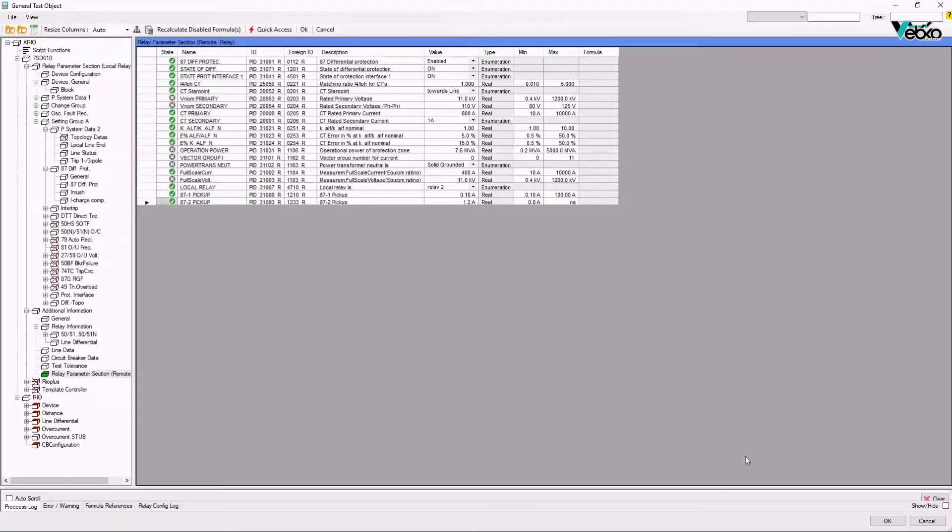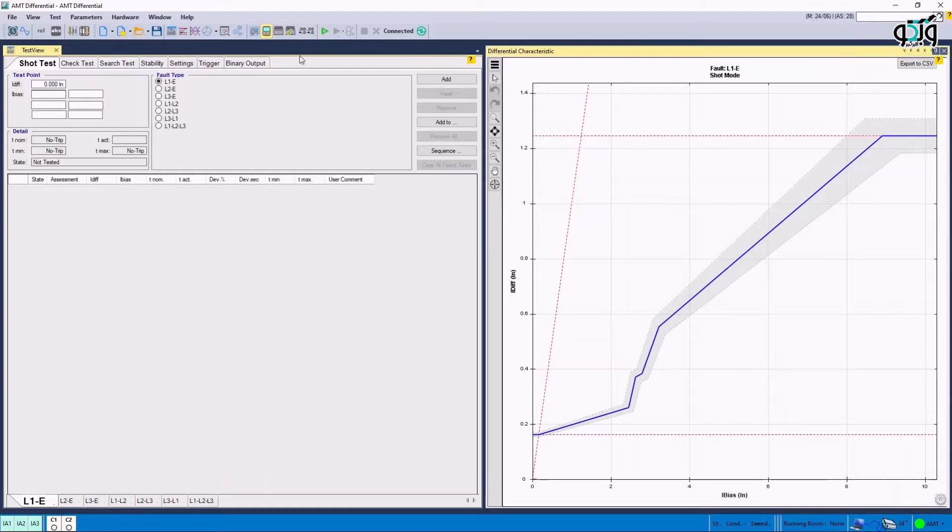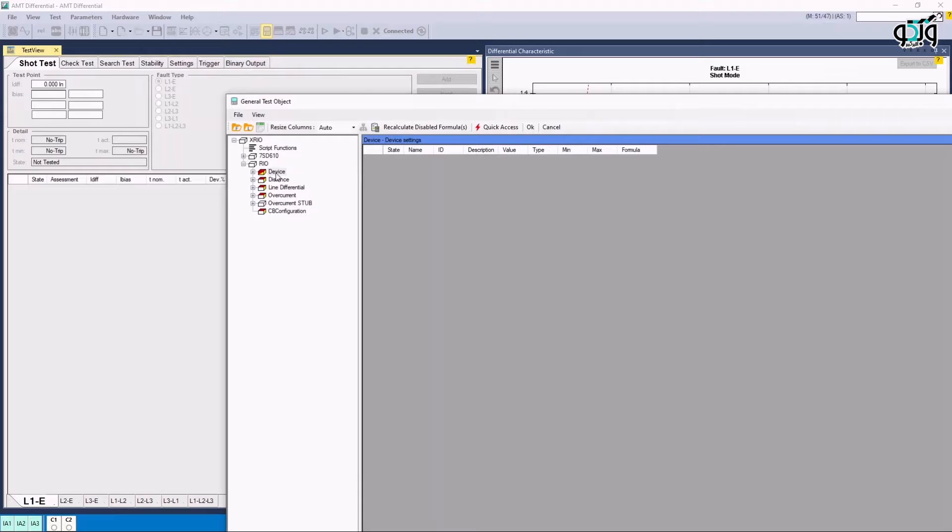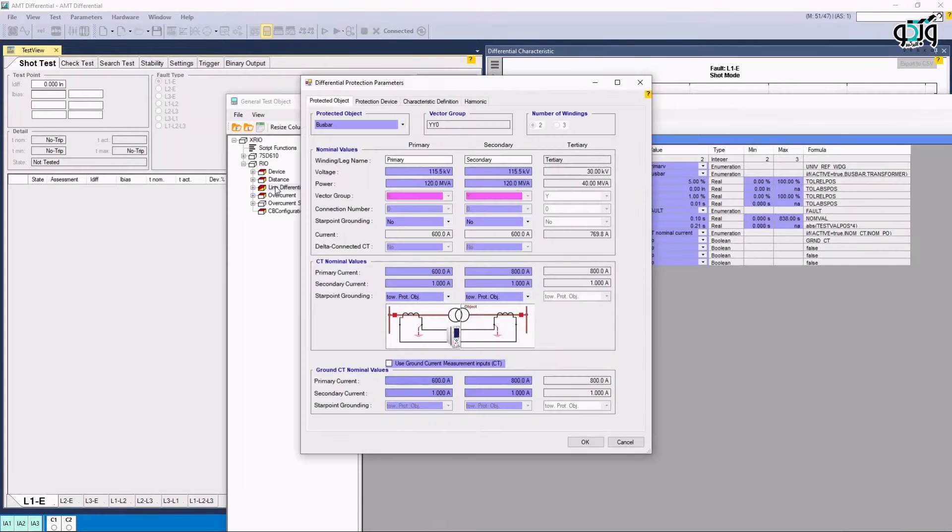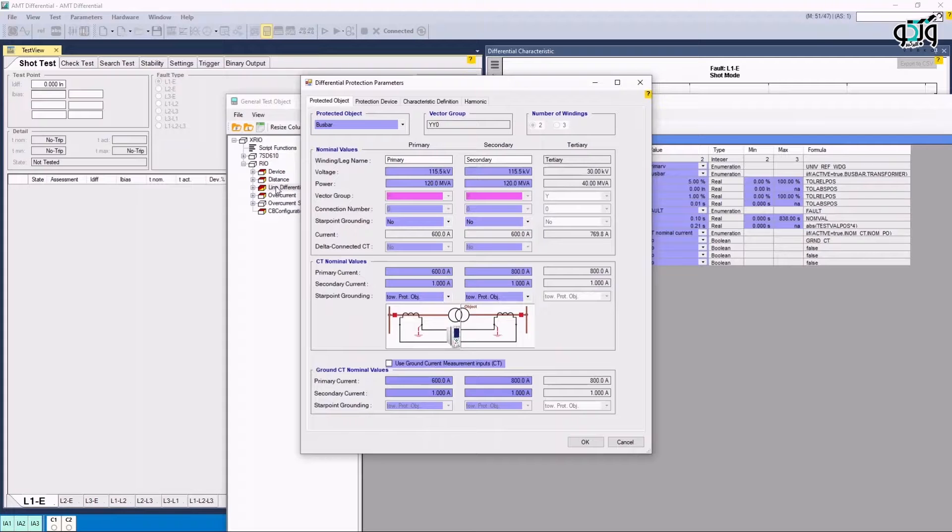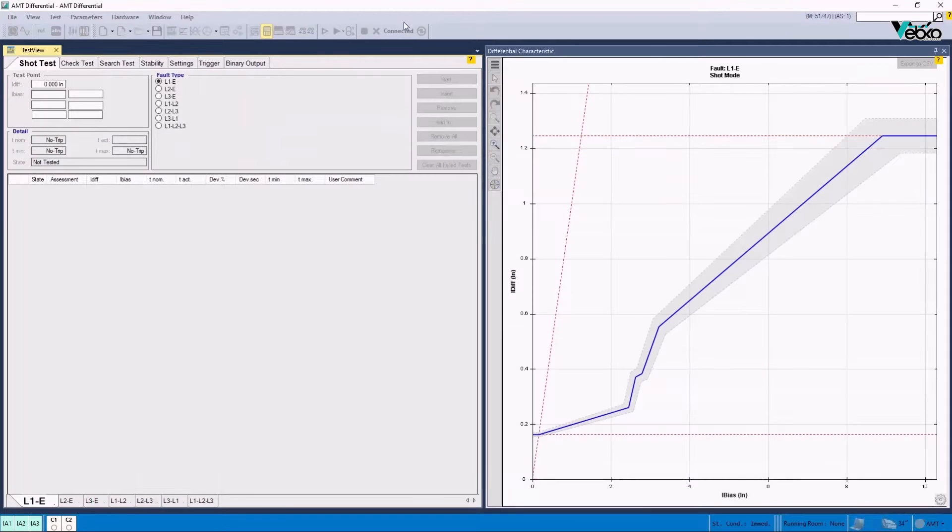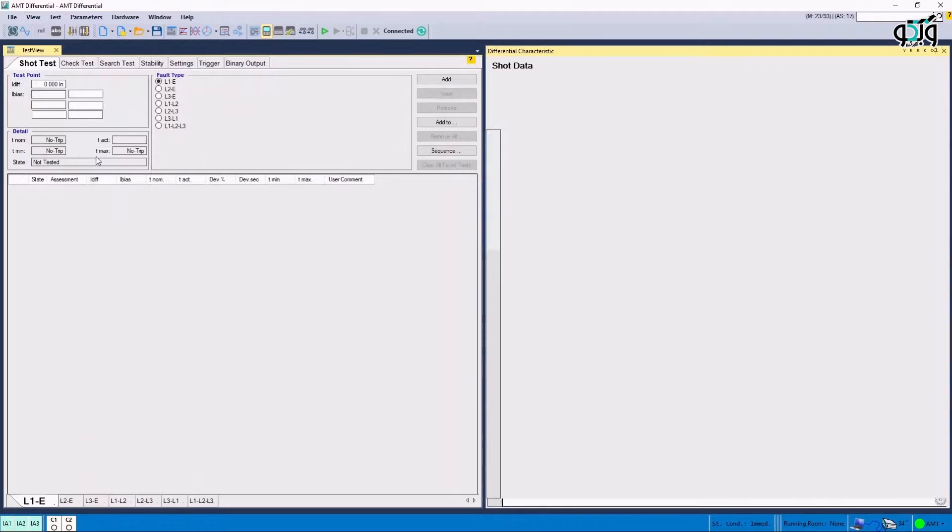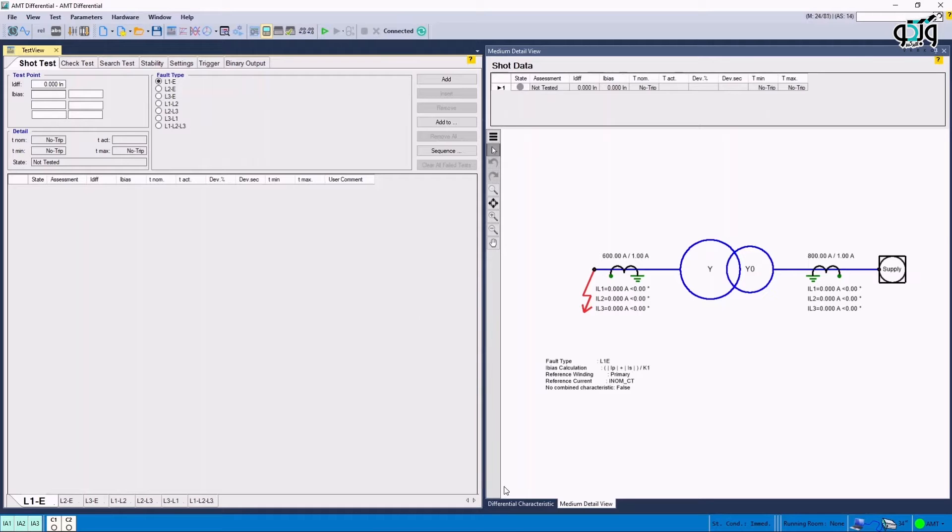Now, once more, Test Object Parameter is selected and Line Differential Block is opened by double-clicking on it. The important point here is that the value entered for primary and secondary in Protected Object section must be the same in both local and remote posts. Also, these values need to be reviewed especially in CT Nominal Values section to ensure that the turns ratio are correct. Also, it is possible to view the test status graphically along with the parameters on it by opening Medium Detail View window from the View menu.